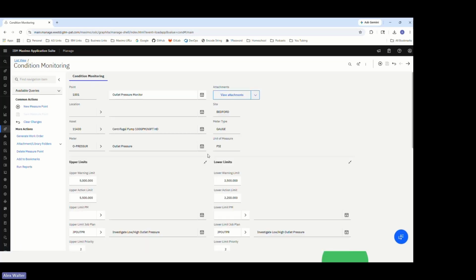So if you've got your Maximo connected to AVEVA PI, you can have Pi readings come in - could be run hours, temperature, or vibration - and you would set up these high and low end bands tied to those gauge type meters in order to trigger work. That's what I had from a show and tell perspective on asset health and condition-based maintenance.